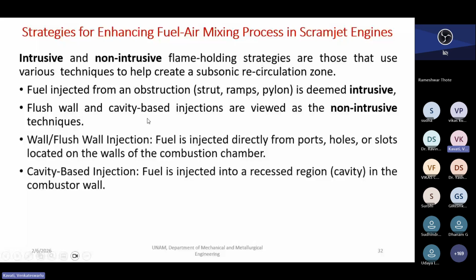So the flush wall injection, basically there are some ports or holes created in the walls of the combustion chamber. So the fuel is injected directly into these ports or holes in the combustion chamber walls. So with this wall injection, the cooling effect is achieved.